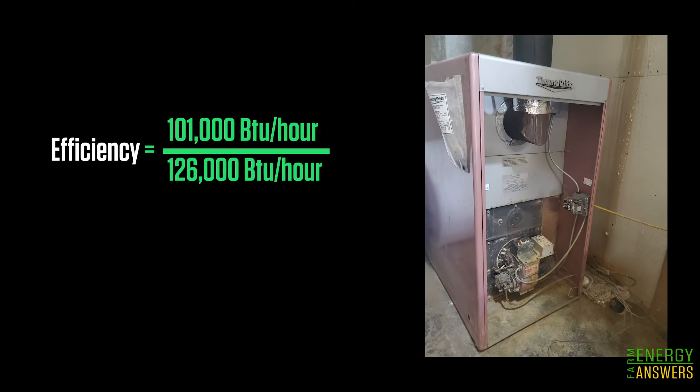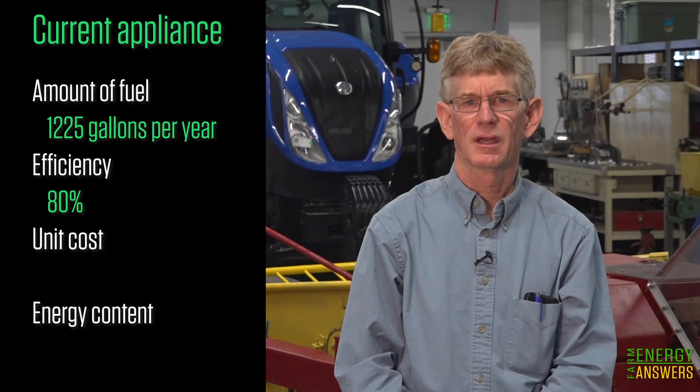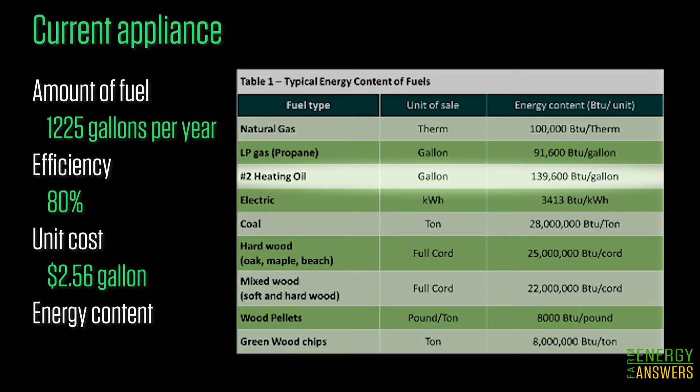Based on this, we can calculate the efficiency to be 80%. Next we need the unit costs and energy content of the current heating fuel. John and Liz's current energy cost is $2.56 per gallon. The energy content of fuels can sometimes be found on your energy bills or you can look them up. From the table you can see that number two heating oil is 139,600 BTUs per gallon.